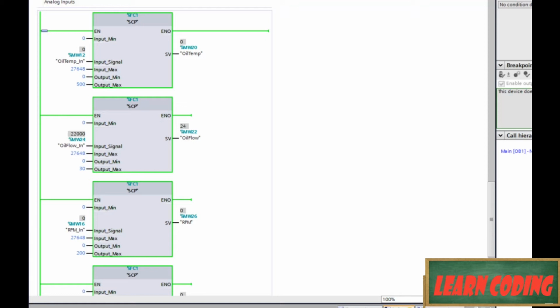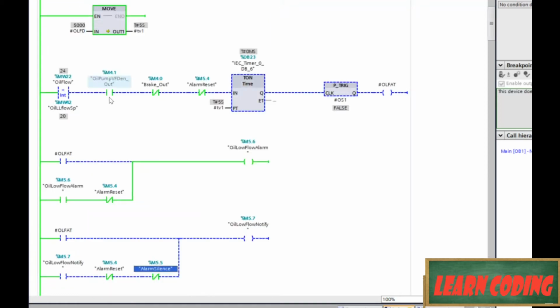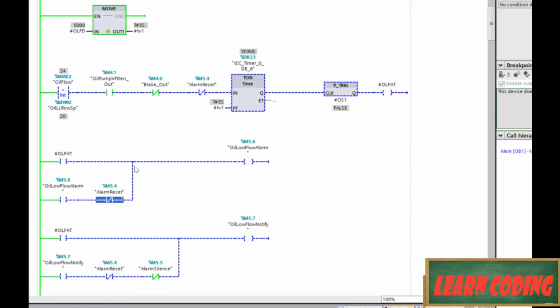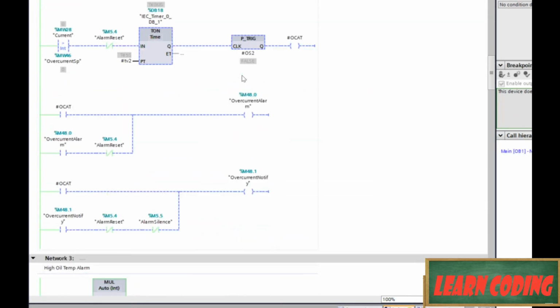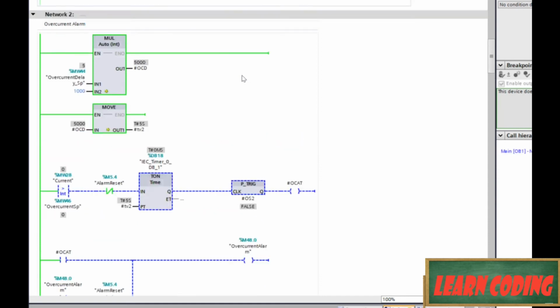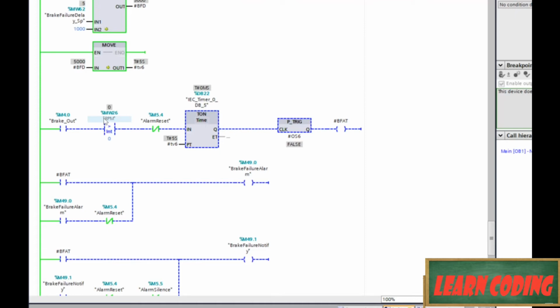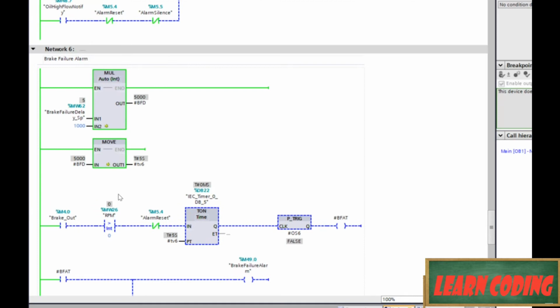Okay, so when we go back into our alarms ladder now, yeah, now we're above that set point. Our alarm remains, and it will remain until we reset. So modify to 1 and modify back to 0. Okay, so that alarm works, and if one of these works, I'm going to assume everything else probably works as well. I do want to look, let's see, for brake failure, I'm looking for the RPMs to be greater than 0.